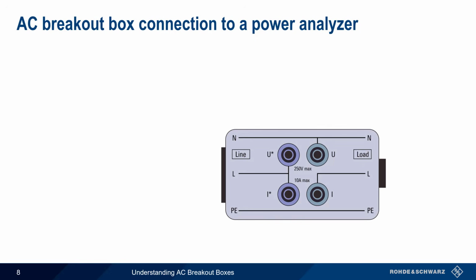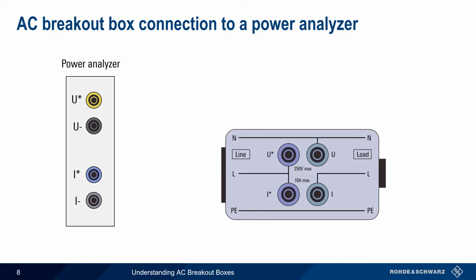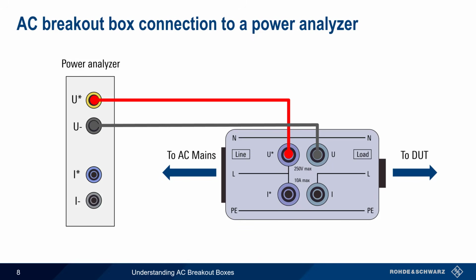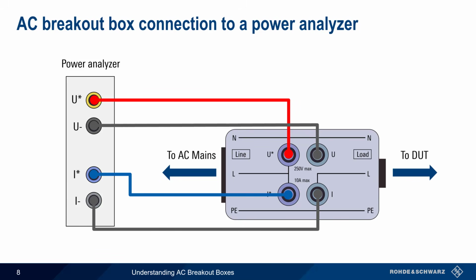Here's how we would connect a breakout box to a measurement card and a power analyzer. As before, the breakout box is placed between AC mains and the device under test. The connections in this case are, however, much simpler than those used with an oscilloscope. The voltage jacks on the breakout box are connected to the voltage jacks on the analyzer, and the current jacks on the breakout box are connected to the current jacks on the analyzer. Note that somewhat different connections may be needed if external probes are used for measuring very high voltages and/or currents.